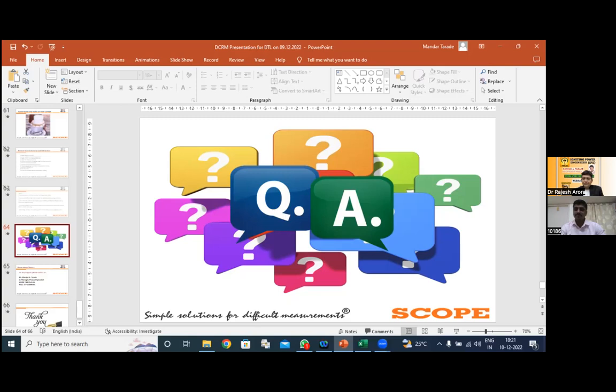For example, learning is a continuous process, as Rajesh Arora ji always tells. And for me today, I learned one important point, signature analysis. Because it's a challenging situation for the industry or establishment due to continuous frequent fire. Why can't we have signature analysis for series arc faults? Series arc faults are not analyzed, not protected, except by arc plus AFDDs that can be used up to 63 amps only. Why can't we have an interactive approach of these people to develop signature analysis for monitoring the healthiness of the installation?